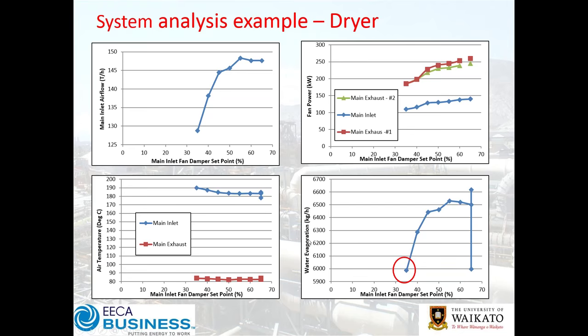The initial set point was 65%. The key driver for the dryer is water evaporation. Starting at around 6 tonnes per hour of water evaporation, we changed a few temperature set points, then with a constant steam valve position, did a series of trials as we changed the airflow and measured the system's capacity. At 35% inlet fan set point with close to a 30% reduction in input fan power, we maintained the same production capacity.